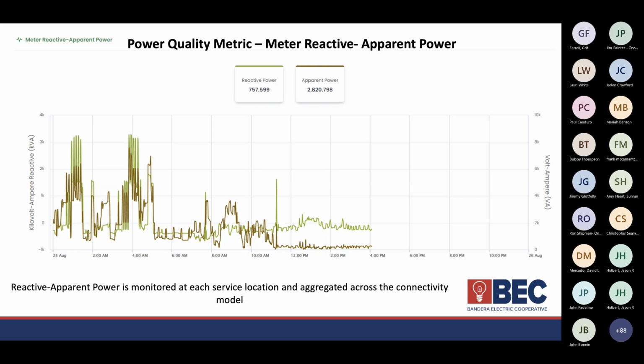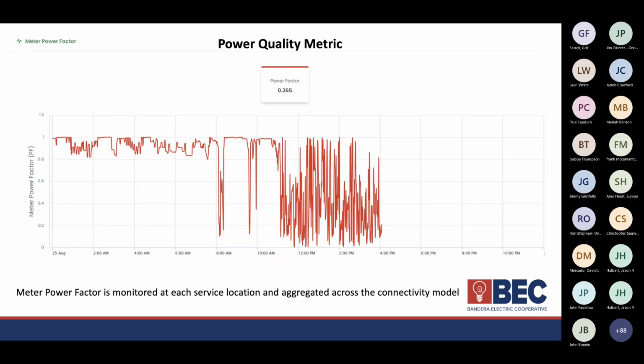This is probably the most important power quality metric engineers think about, the power factor. It's a very tight range when power is coming off the grid, and it gets really spiky once generation starts being injected onto the grid. That could be the quality of the inverter, I think that's a lot to do with it, but I won't opine on why. We just measure it, and it helps us if we start having issues on a certain feeder.